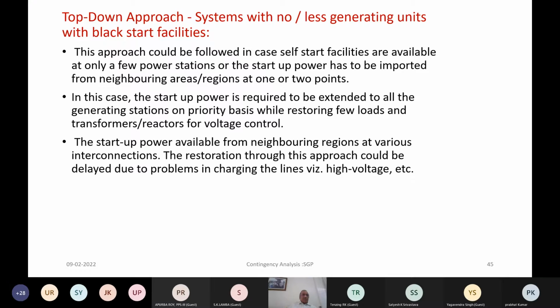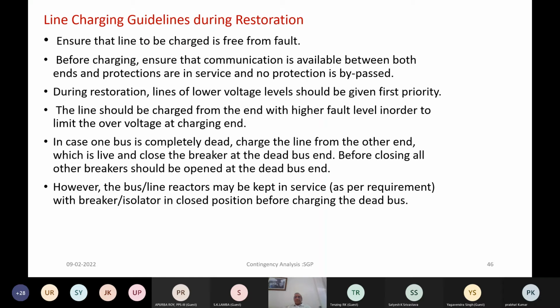This can also be done not only within the region. That means if, say, the northern region is totally shut down, then the eastern region or western region can provide startup power to the stations in the northern region. So this is a sort of top-down approach. That means you start with 400 kV and then go down to lower voltage at the distribution level. So that is the top-down approach. Then next is the line charging guidelines during restoration.